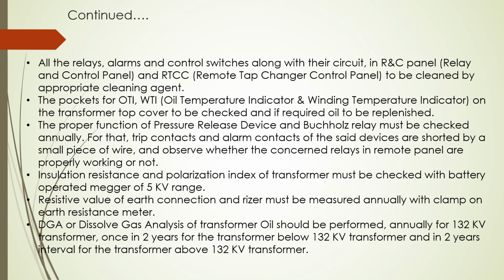The proper function of pressure release device and Buchholz relay must be checked annually. For that, trip contacts and alarm contacts of the said devices are shorted by a small piece of wire and observed whether the concerned relays in remote panel are properly working or not. Insulation resistance and polarization index of transformer must be checked with a battery operated megger of 5 kV range. Resistive value of each earth connection and riser must be measured annually with the clamp on earth resistance meter.